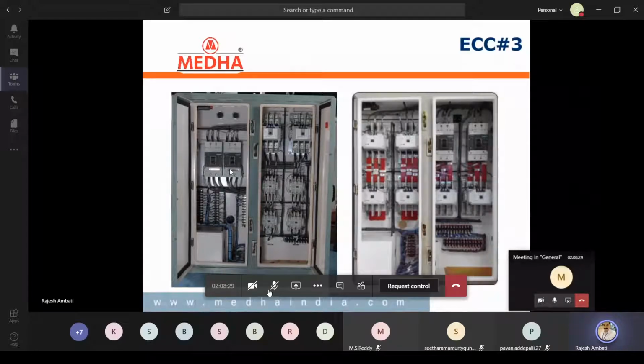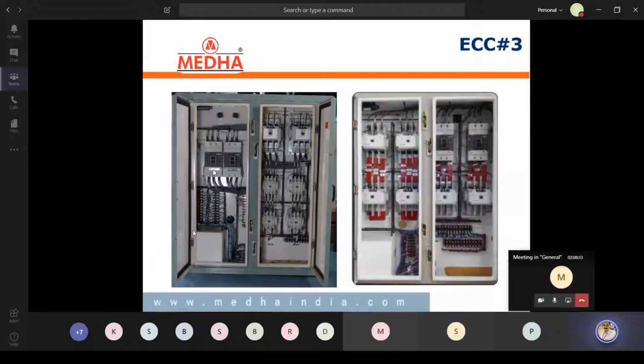So here internally, for the MCCB operation, 3 potentiometers were there in the old and 2 potentiometers in the new contactor. Those are factory set, we have adjusted. You should not change that without any information. During maintenance, if any problem is there, we have to check these potentiometer settings as per the standard. These are multi operated circuit breakers, so by setting some value, we are operating at different currents and different time values. So overall, this is about ECC3 electrical control cabinet, which is placed just beside the compressor room, old and new model both.